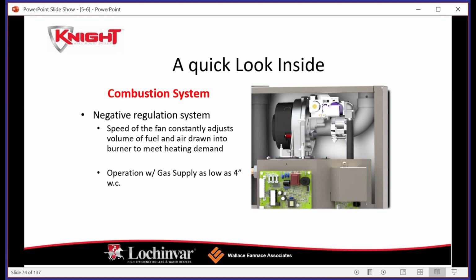As you're looking at this little excerpt of the inside of the cabinet, on the right-hand side we have our gas piping that's supplying our gas, again, from 4 to 14 inches of water column. It's going to flow through the gas valve into the fan where it's mixed with the fresh air, right? That combustion air that we're pulling from outside, or possibly from room air, depending on if you have enough room to satisfy the BTU inputs on the boiler.